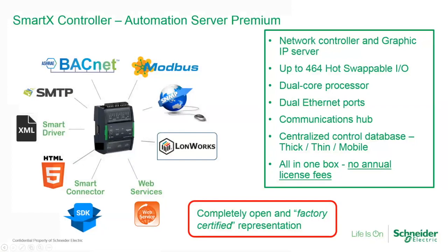We're at a point now with this automation server where, out of the box, we could run a trunk off this controller communicating BACnet and another trunk communicating LonWorks. So if you have a facility with LAN, you could run a trunk that communicates LonWorks, and everything new can be BACnet. You can also communicate Modbus out of this, and web services, so we can bring in information like energy pricing or weather data. And really importantly, we can connect via our Smart Connector to third-party applications and services.